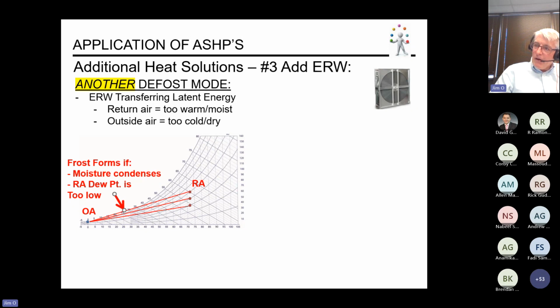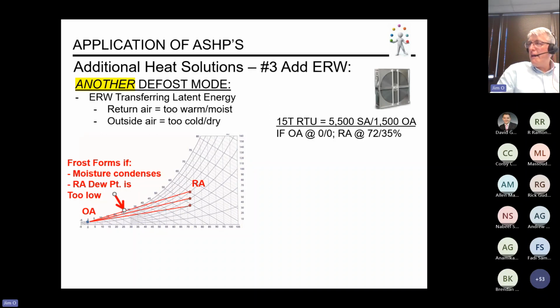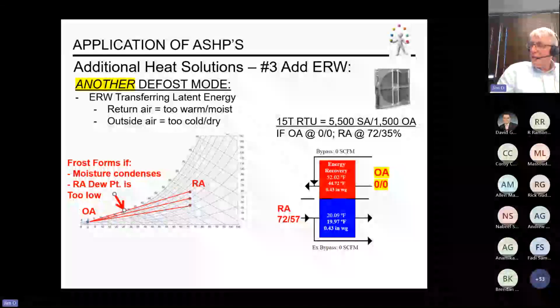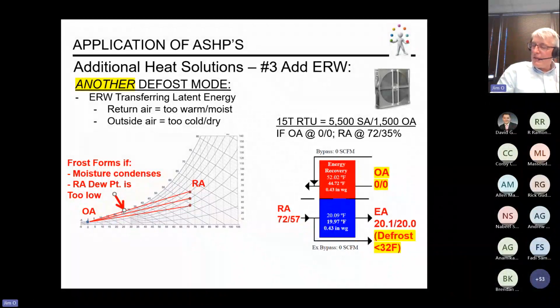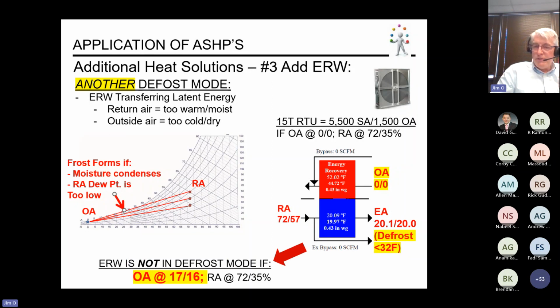And if the line drawn there on the system crosses over our saturation line, and it's below 32 degrees, we'll have defrost. So back to our 15-ton unit, with those outside air and return air conditions from the program, we end up demonstrating that my exhaust air temperature is below 32. We're going to end up with defrost on our energy recovery wheel in certain situations.